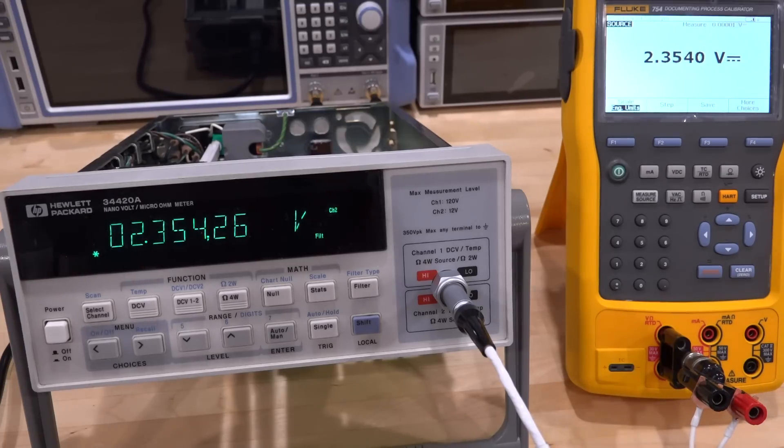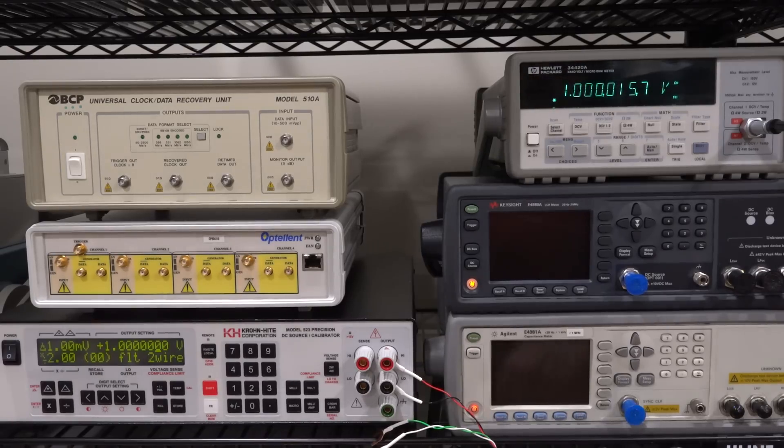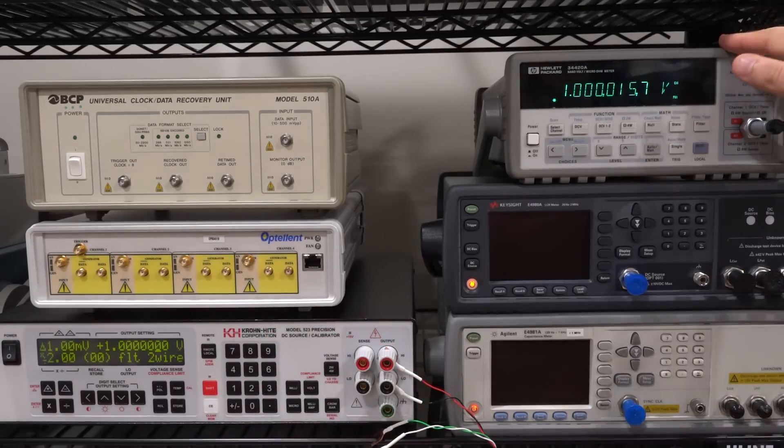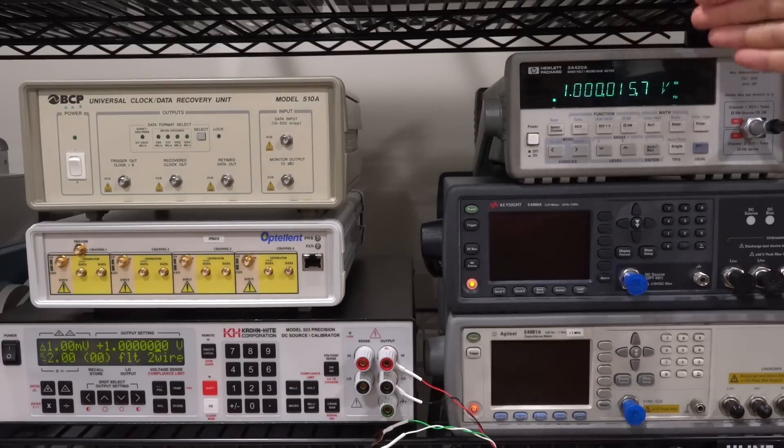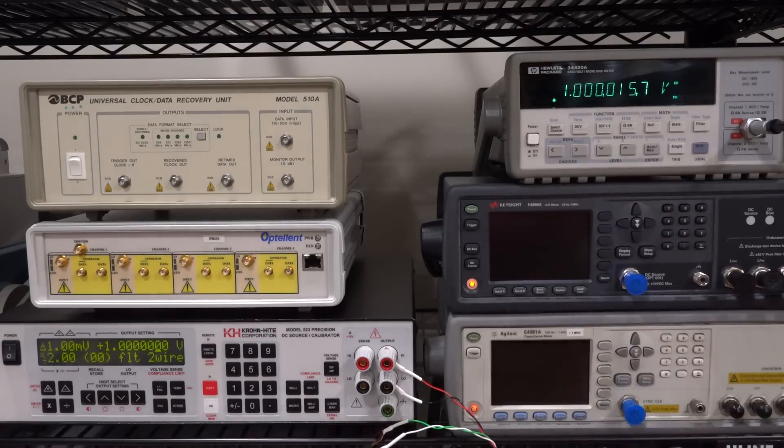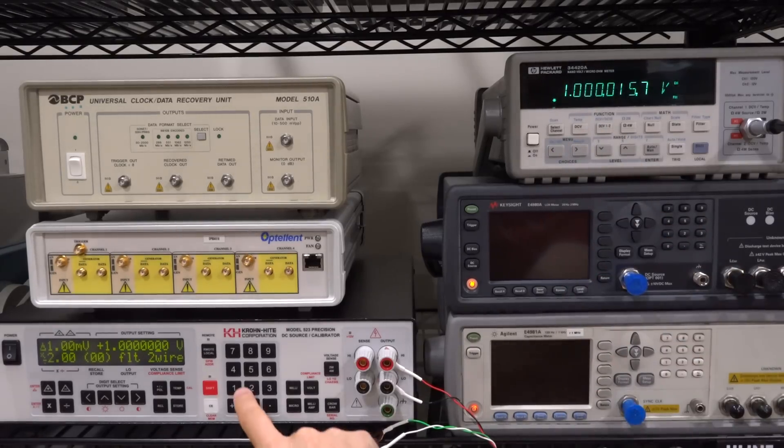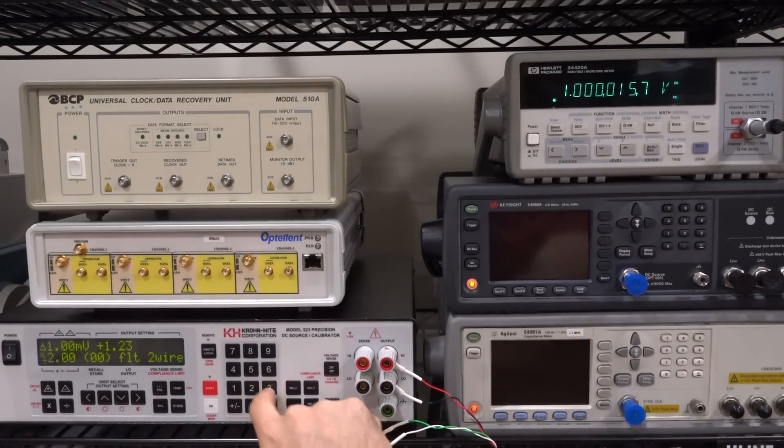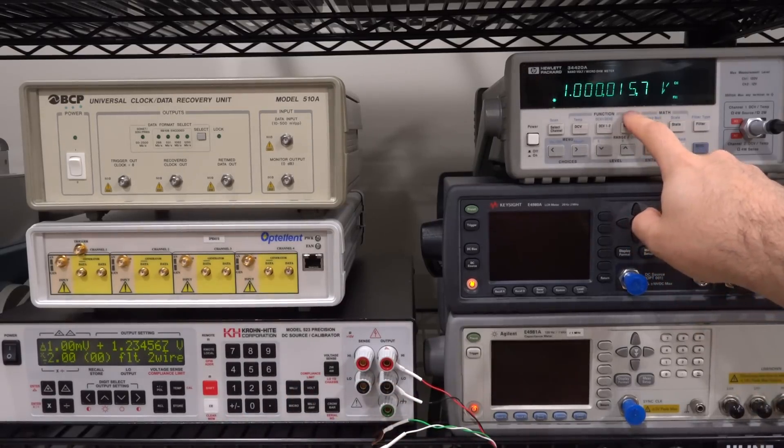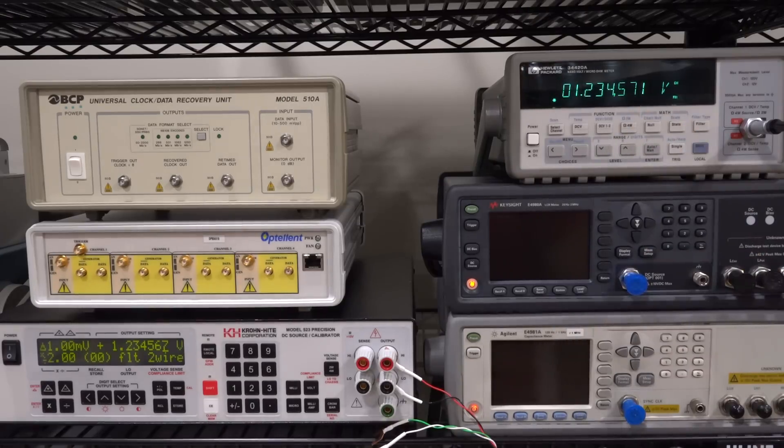Here we are. I have it connected to the Krohn-Hite model 523. Both have been warmed up. You can see it's measuring quite good - only 15.7 microvolts out. This itself needs a bit of calibration, so this may even be closer than shown. Let's try a different value - 1.234567. We should read almost the same offset in that voltage as well. There you go, look at that. Not that far off. I'd say pretty good considering we worked on it.